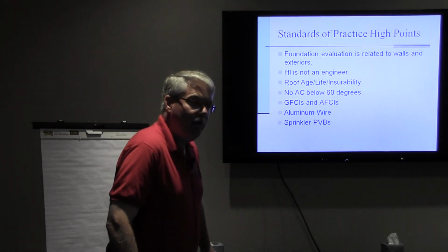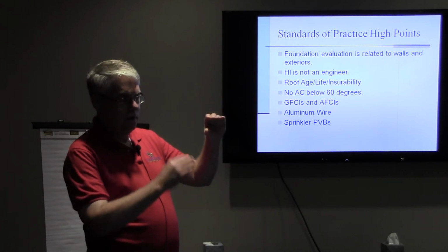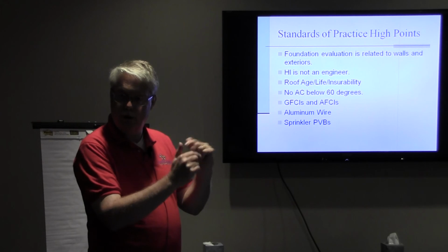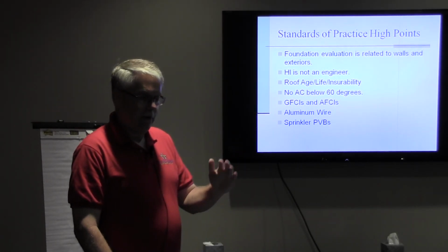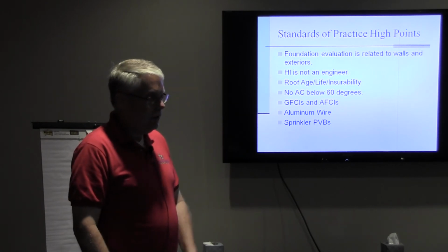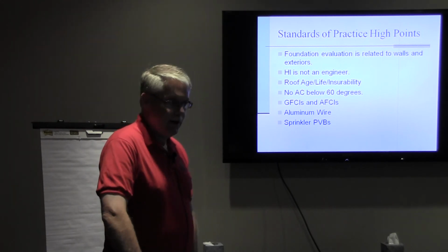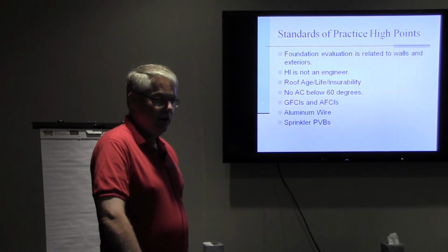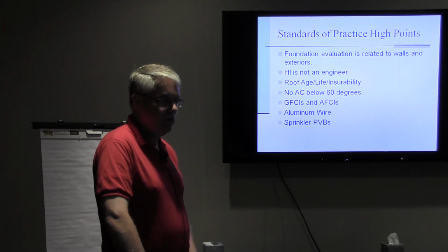The other thing about arc faults is you'll see about half your electricians will space an arc fault with a non-arc fault outlet, because if you stack 4 arc faults, they're bigger, they warm up, and they burn each other out in an electric panel. So you find electricians who will space them, which causes a labeling coordination issue. It just is frustrating for them. I did a house Saturday that had 16 arc faults, and there was not enough room in the electric panel to space them all out. So I had explained to her to be a little watchful of it. New construction on East Shore.